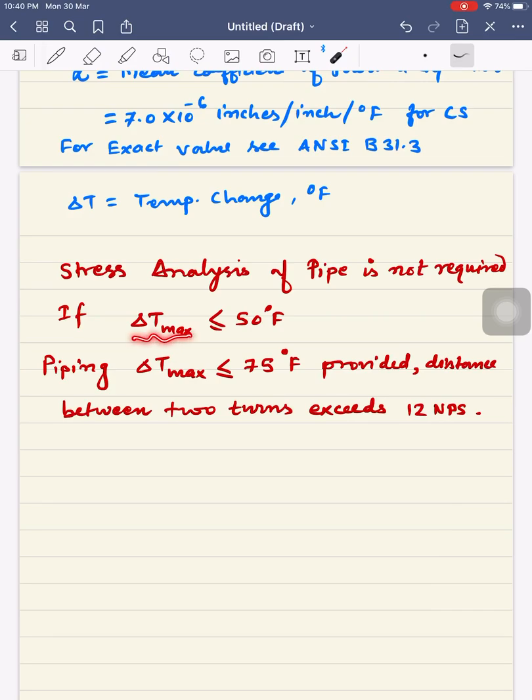There are some other rules: stress analysis of pipe is not required if delta T maximum is less than or equal to 50 degrees Fahrenheit, or if delta T maximum is less than or equal to 75 degrees Fahrenheit provided that the distance between two turns exceeds 12 nominal pipe sizes.